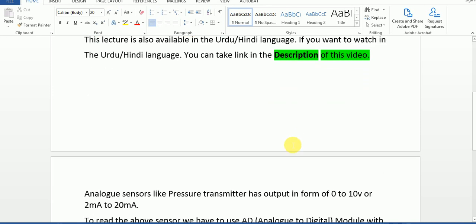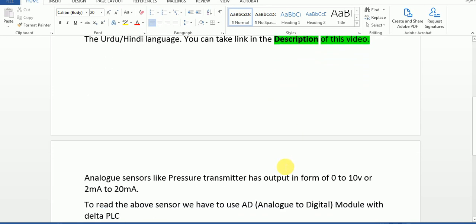As we know, there are two types of sensors: one is a digital sensor and the other is an analog sensor. A digital sensor has only output 1 or 0, meaning 0 or 24 volts. But an analog sensor like a pressure transmitter has output in the form of 0 to 20 volts or 4 to 20 milliamps.